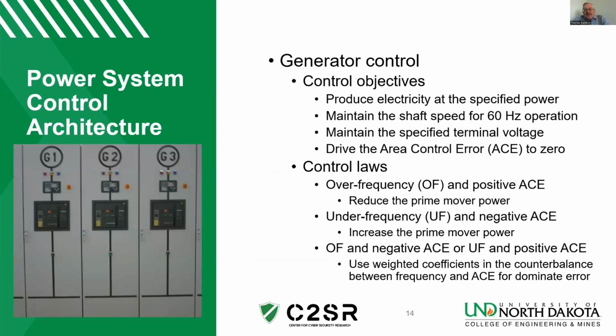The control objective of our generation is to provide 60 hertz or 50 hertz power as specified by each different area, maintain voltage, and drive the area control error for a utility to 0. This is our balancing rule. We have control laws for making adjustments when we have too high or too low frequency. Over frequency and a positive area control error basically says we have too much power, and so we must reduce what we're delivering from the prime mover of the power plant to the generator. So we control the set point of the governor down.